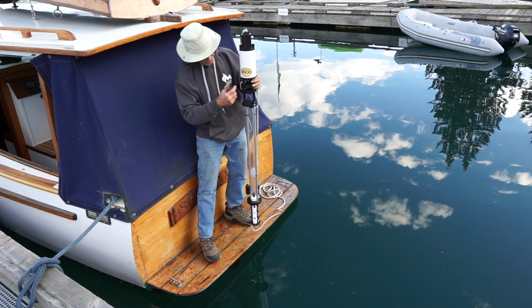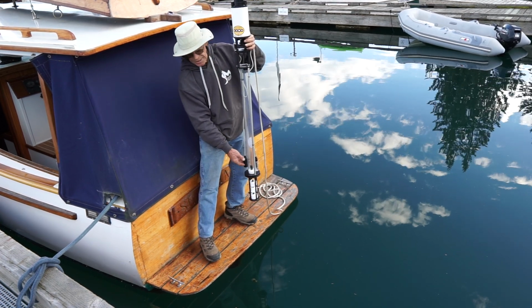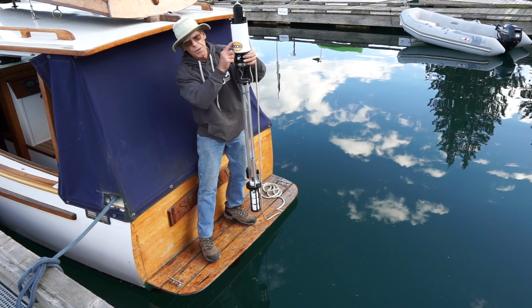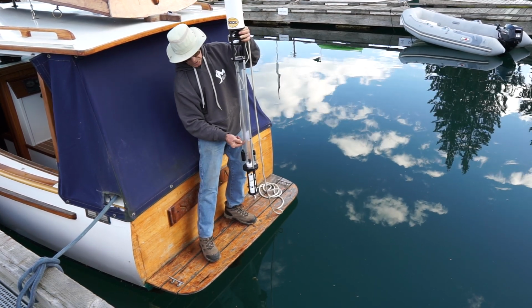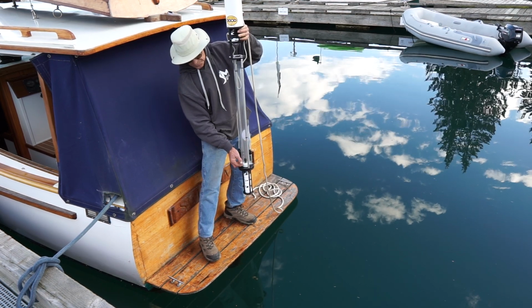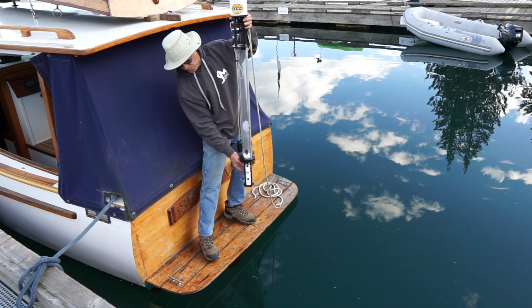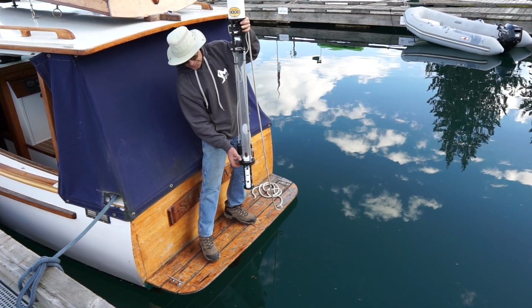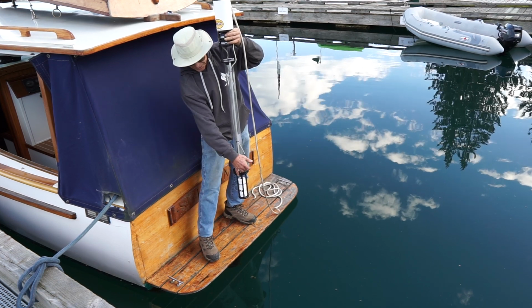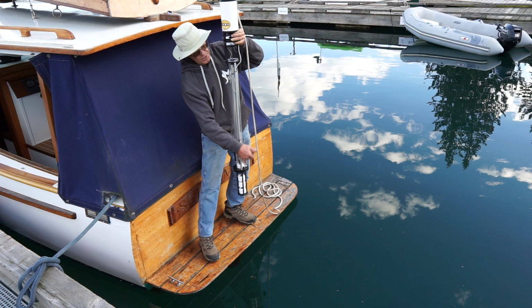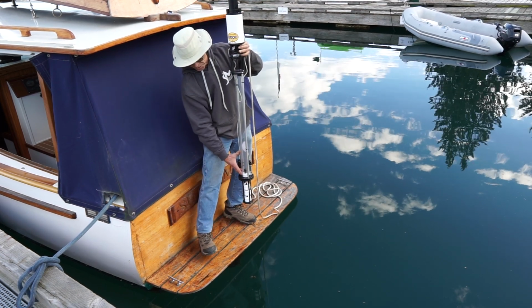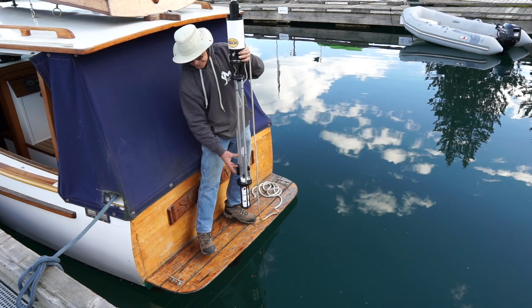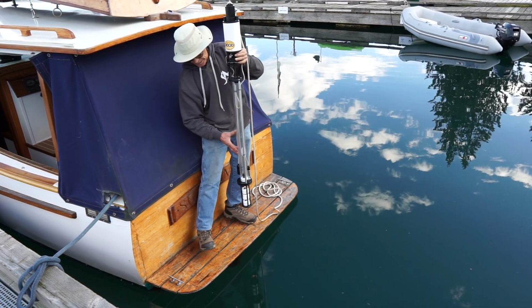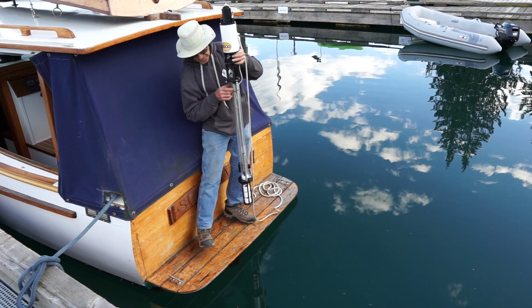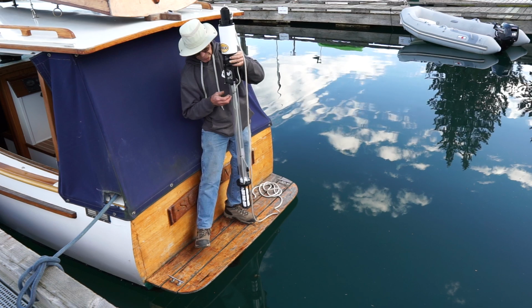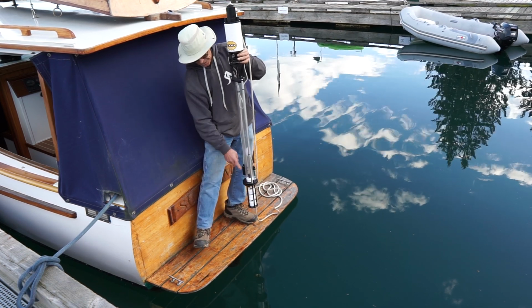There's a pressure transducer here that when it gets to 3 meters, turns on the winch, which lifts this first plug up into the column. The water directly below the plug follows the plug in. The second plug, which is attached to the same lift wire, enters the tube, and once inside, it's shut off. The optical sensor sees it and shuts off the winch. So we collect the first sample here, we lower to our next step, collect our second sample, which moves our first sample to midpoint, and then finally to our final third depth, which then we have 1, 2, and 3 samples, or first sample, second sample, third sample.